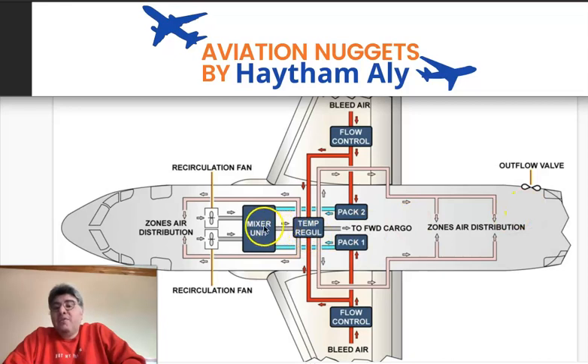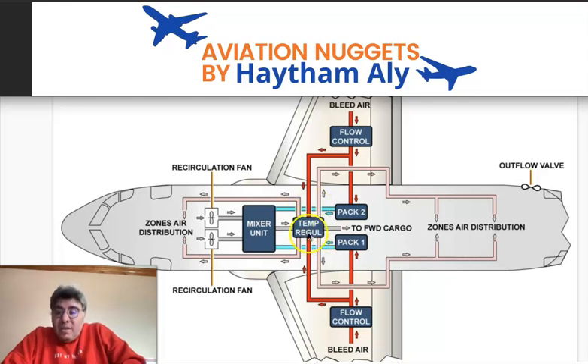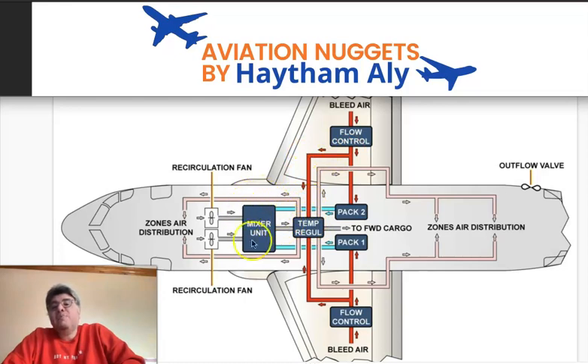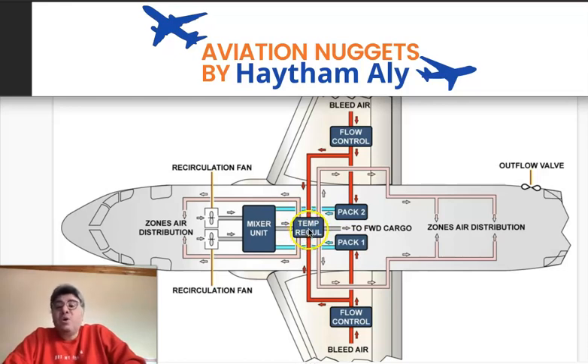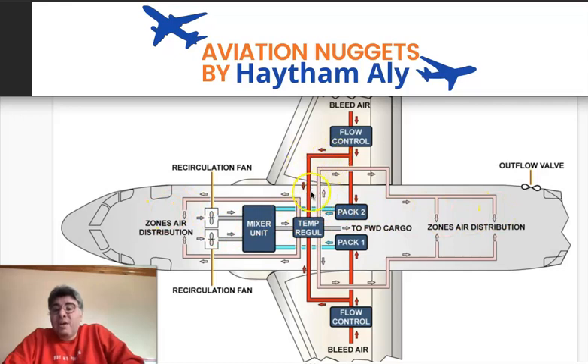Before air travels from the mixer unit into the three zones, the enhanced or optimized temperature regulation takes place. Hot air — shown as a red arrow — coming from before the packs is added to the air from the mixer unit. The main components are one hot air trim pressure regulating valve and three trim air valves, one for each zone.